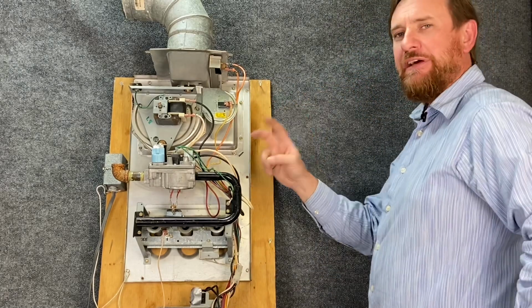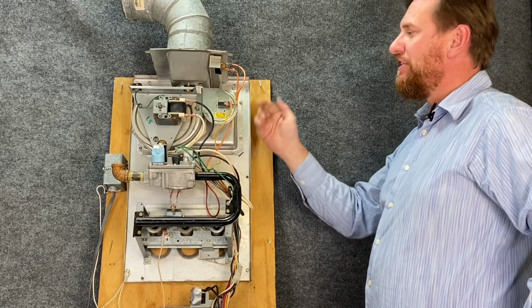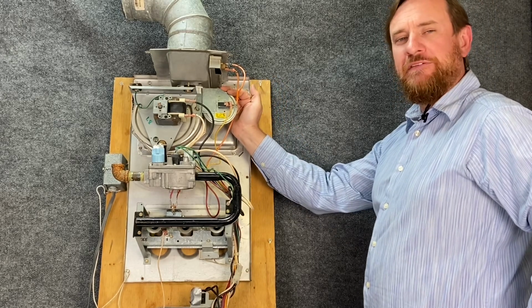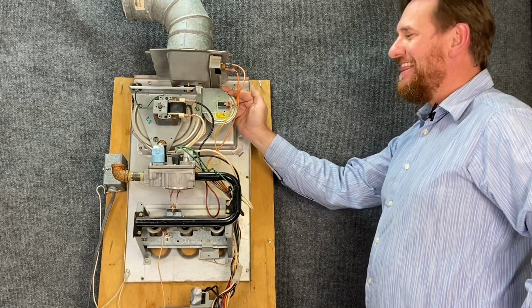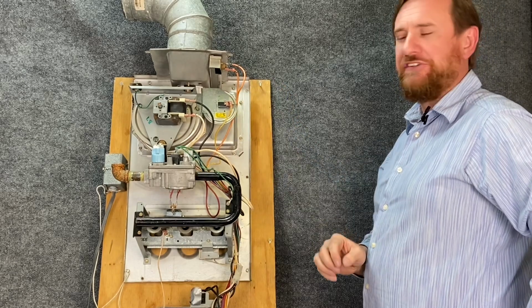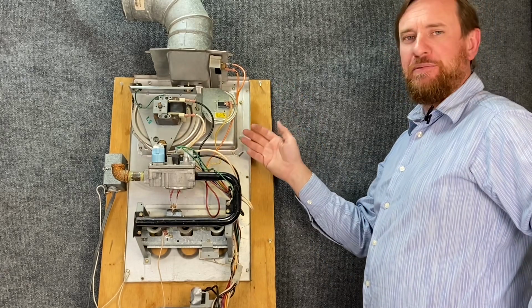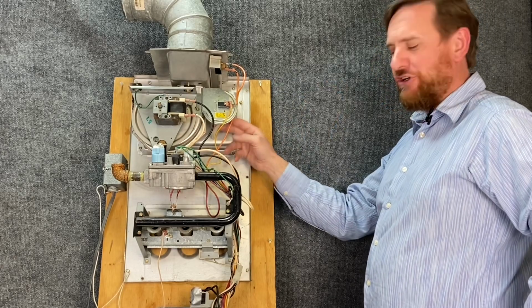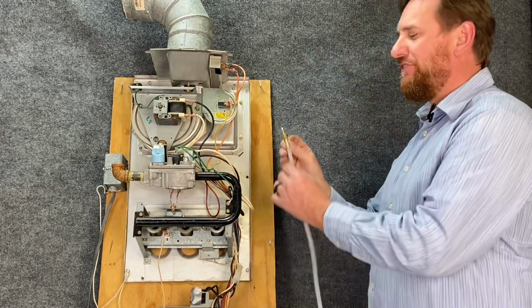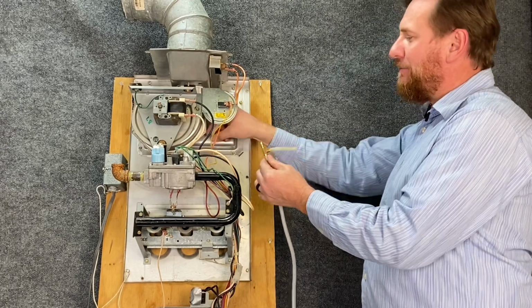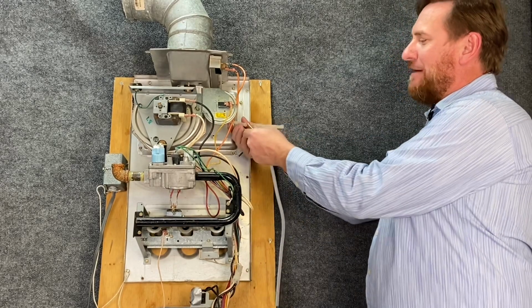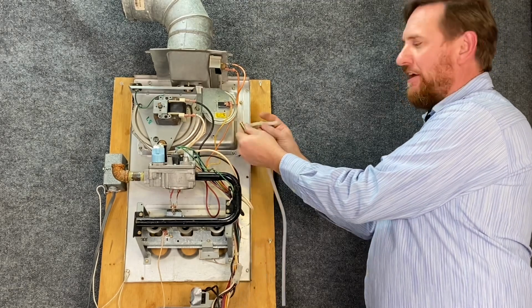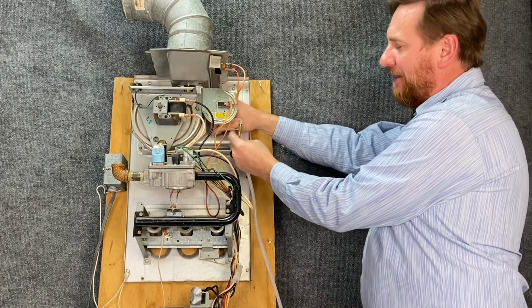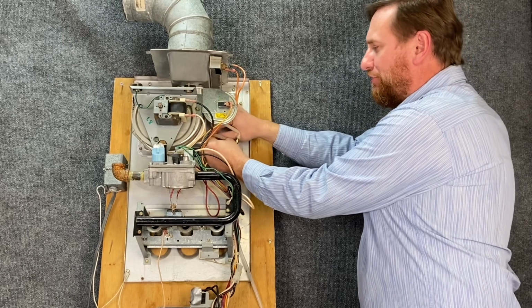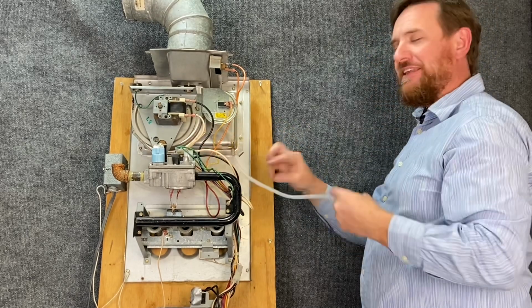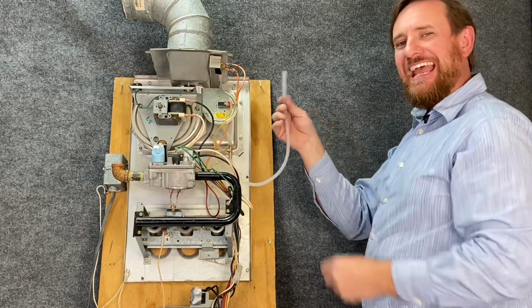This switch, we need to think about it as a pressure and a switch. So we need to make sure, do we have the proper vacuum coming to the switch first? Then if we do, let's see if the switch closes. So we're going to fire this system up and go through that process. But how are we going to check to make sure we have that happening? What we're going to use is this nice little brass T. I'm going to unplug the existing hose and connect it to my brass T. The other hose on the side is going to go back to my inducer fan motor, my inducer draft, so it's pulling a vacuum. That's also going to pull a vacuum to this third hose.